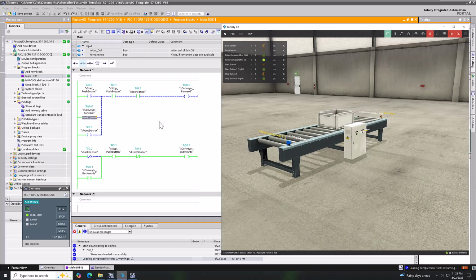You can see it right now in the state that the front sensor is on. The front sensor right here is on when it gets made, and then the back sensor is on all the time until it gets made. So you can see those are in different transitions, right? One is basically on when there's nothing in front of it, and one is off when there's nothing in front of it. So you have to use those as normally open and normally closed contacts in the PLC program to actually see the benefit from that, or to use it properly.